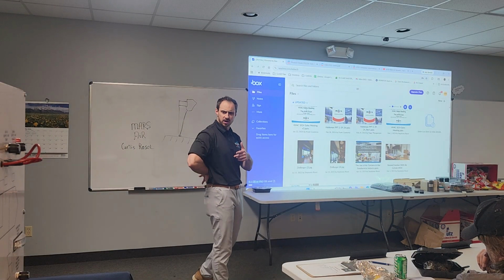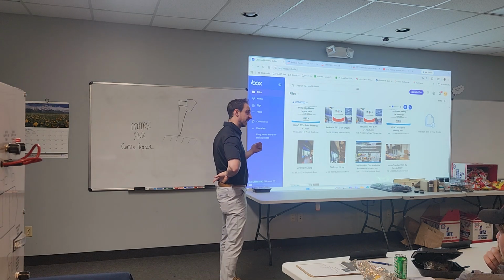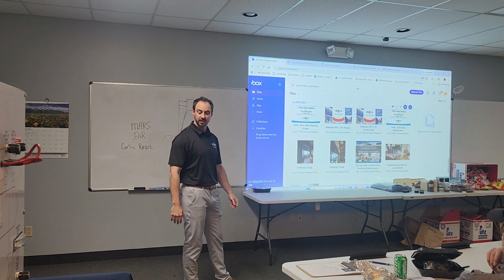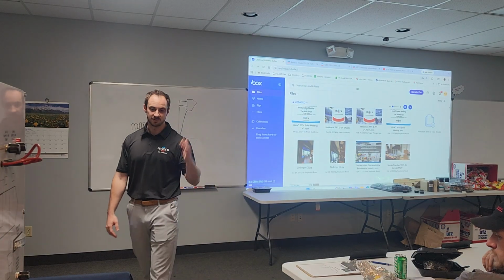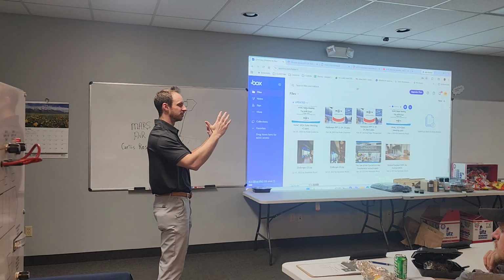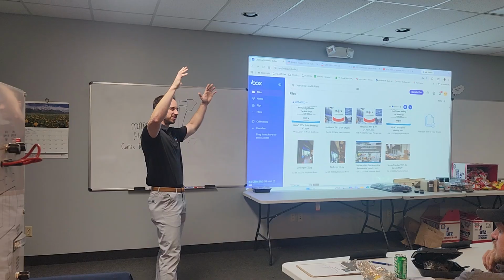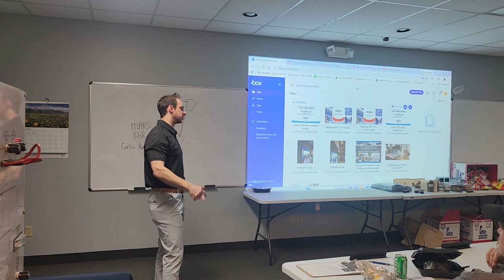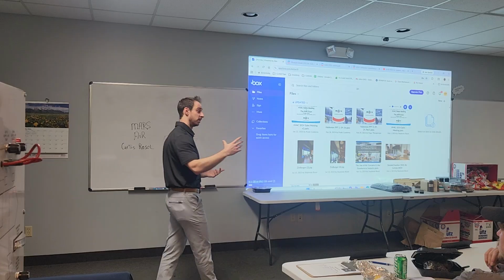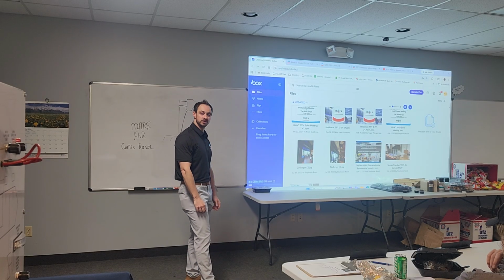The one I was talking about earlier, I unfortunately don't have an image of on the Box link, but it was that Campbell's project, and I think that was somewhere in Ohio. They did a vertical unit. I wish I had an image of that. The door was 16 feet tall and super narrow, so it didn't make sense to put the unit above it because they didn't have the space. So we just did a longer unit with less horsepower essentially, installed the vertical on the door, and got really good results with that too.